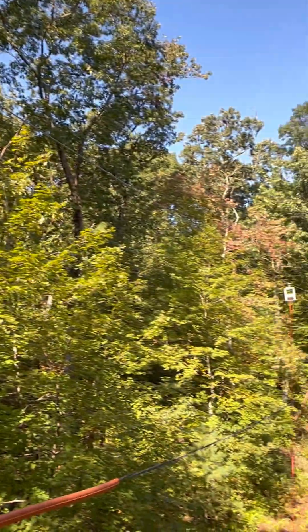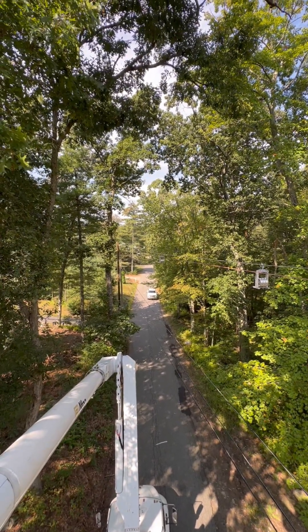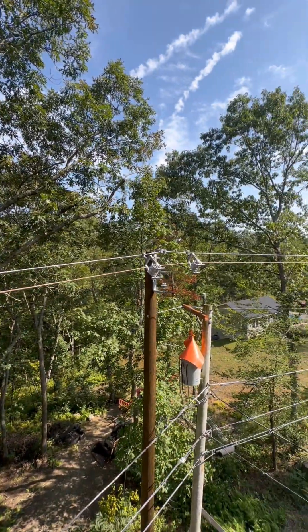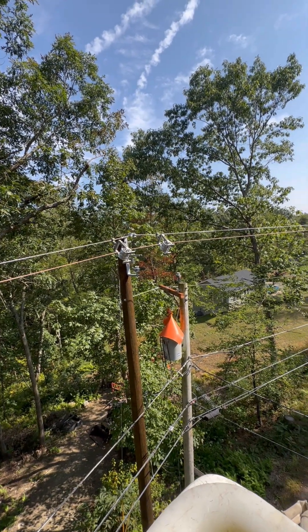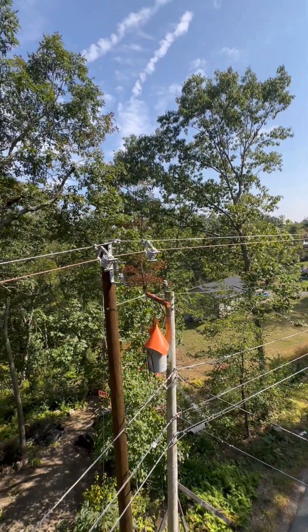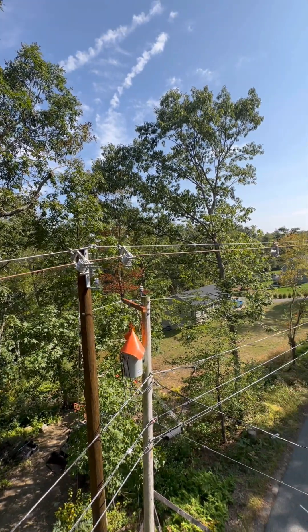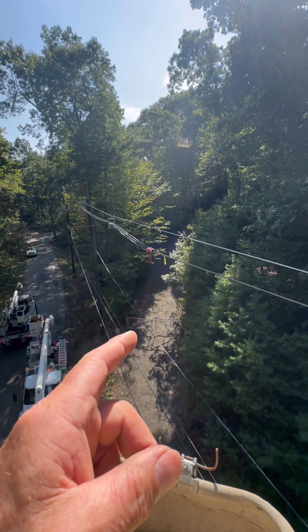Basically, fixing to pull wire. We got our bull rope in and had to set up on all these poles through here — pretty wicked angle. It's ping-pong, across the street, bing bing bing bing. We had to add a second roller to bisect this angle and kind of soften it up. It's pulling on it pretty hard — we'll see how this goes. This is called the gator block.